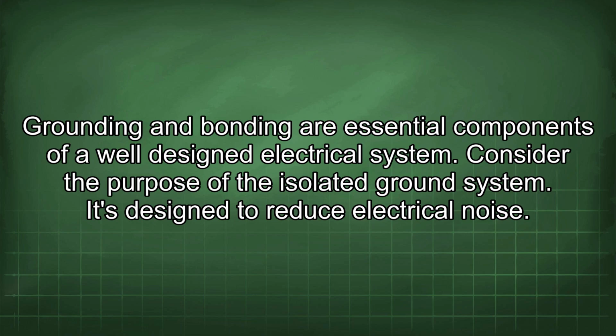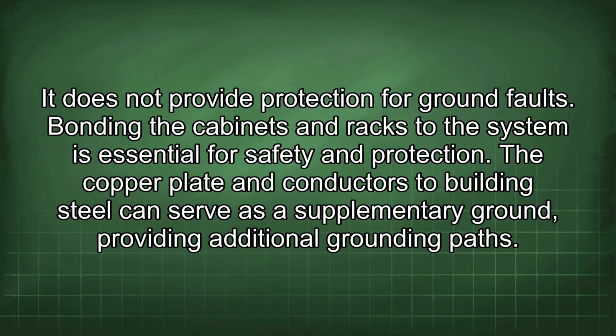Consider the purpose of the isolated ground system. It's designed to reduce electrical noise. It does not provide protection for ground faults. Bonding the cabinets and racks to the system is essential for safety and protection.